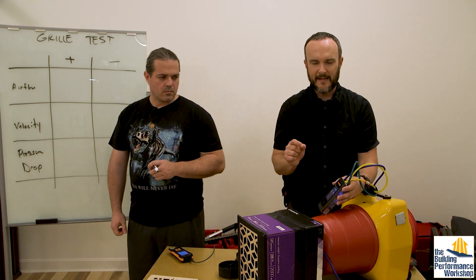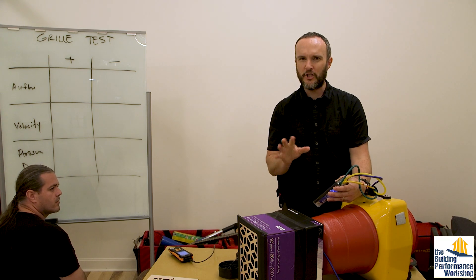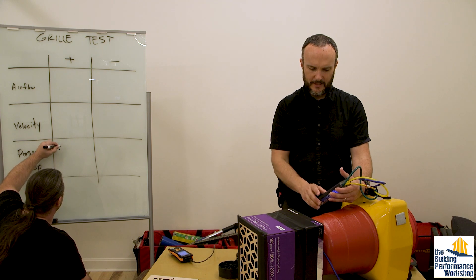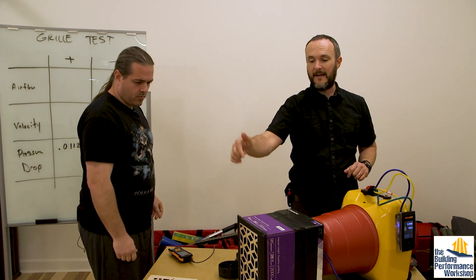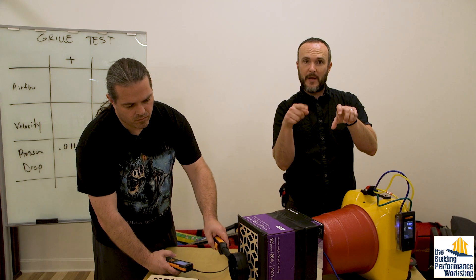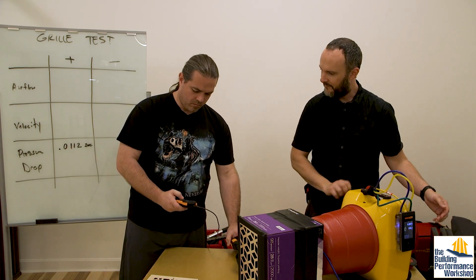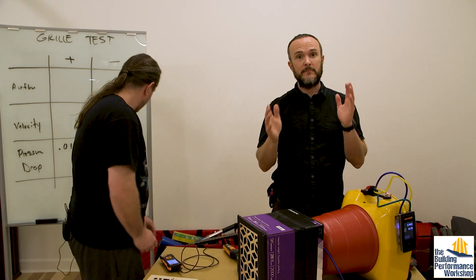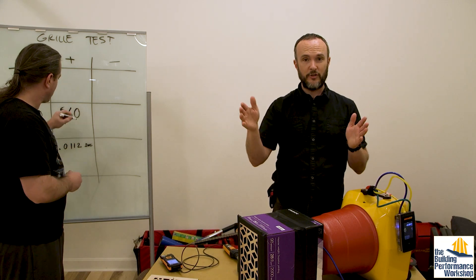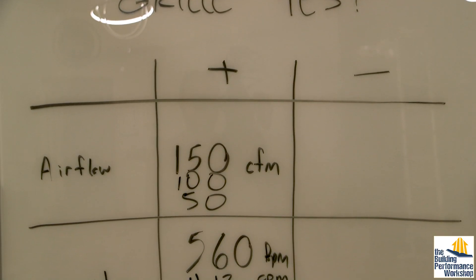At 150 CFM we've got a pressure drop of about 0.0112 inches of water column — I made the time average longer to even things out and settle the number. Now we're also going to verify the CFM with a large vane anemometer and get the velocity at the same time. Scott's taking a timed average — you want to let the anemometer ramp up to full speed before you hit start, then pause it. We're looking at 560 feet per minute, which is great: 500 to 700 feet per minute is the ideal range for a supply grill.